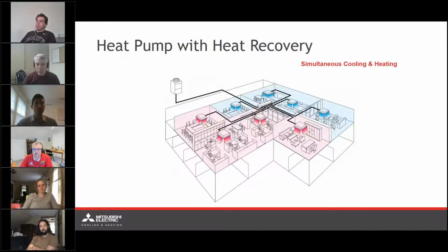Now, as opposed to heat pumps, we also have our heat recovery series of equipment. Heat recovery is where you are going to get the capability for simultaneous heating and cooling on one single refrigerant network. And the difference that we're looking at here is the introduction of this additional component right here, I'm circling with my cursor, central to the system. That's what's referred to as the branch circuit controller.